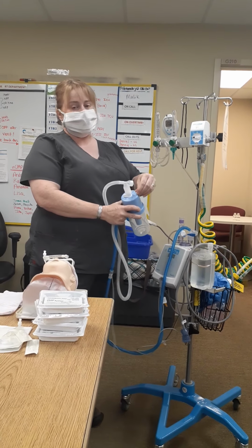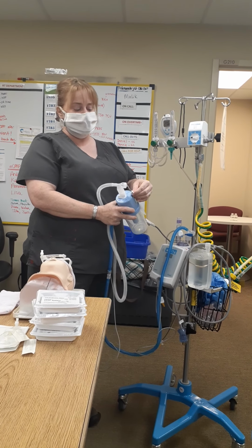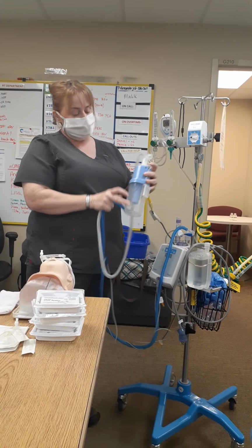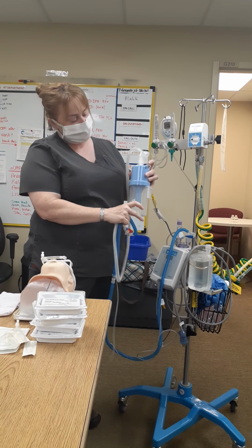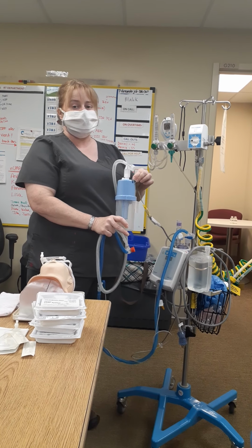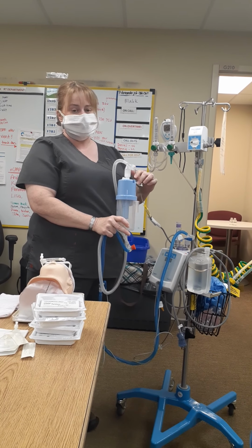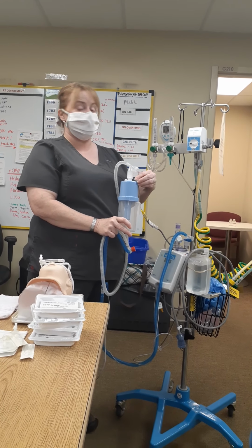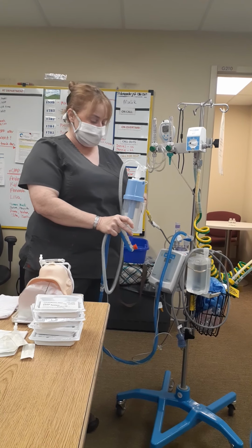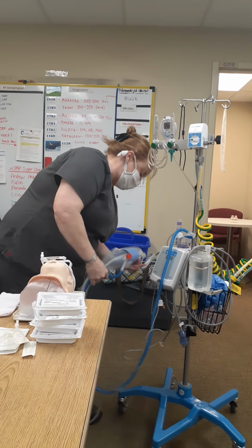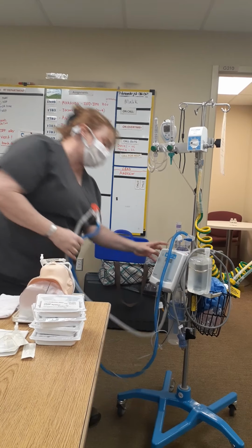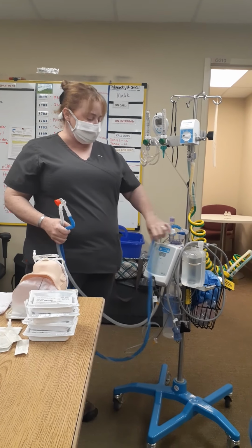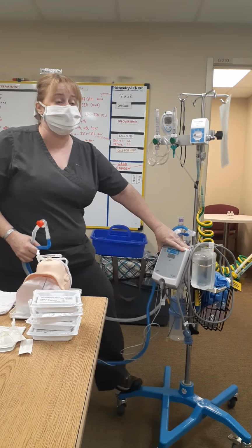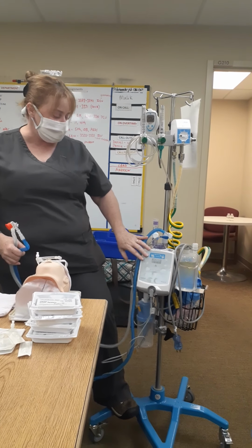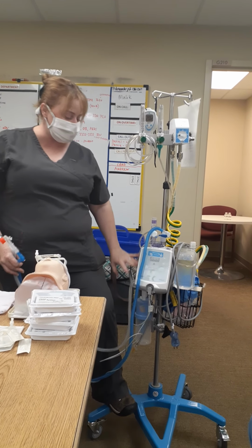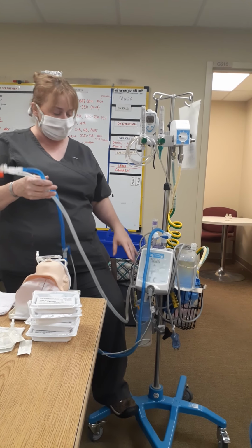This is the little white cap, which can also be a source of leak. So if you do want to add or remove water, there's a little straw down in this bottle that you can add or remove water with a slip tip syringe through this. And we will keep a syringe with all of these setups so that we have that. The heater is our usual heater, which we're going to set on 36 or 37 depending on the baby. We want to make sure that your water bottles are always below the infant.